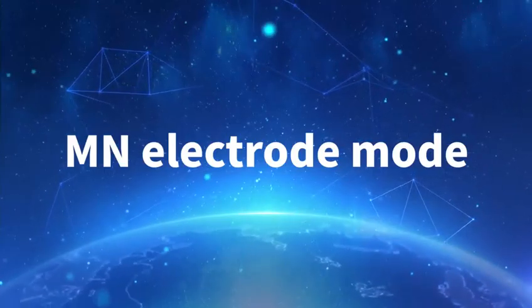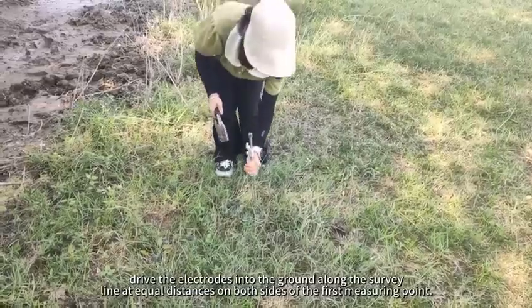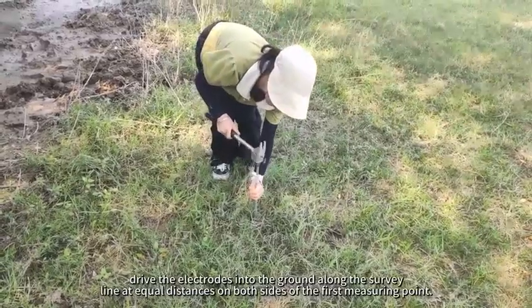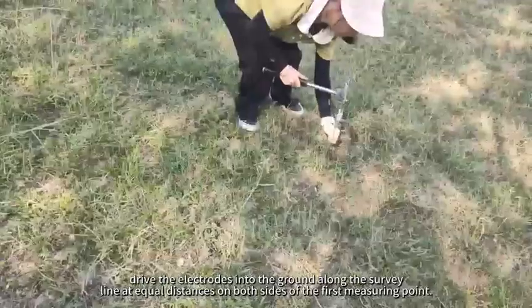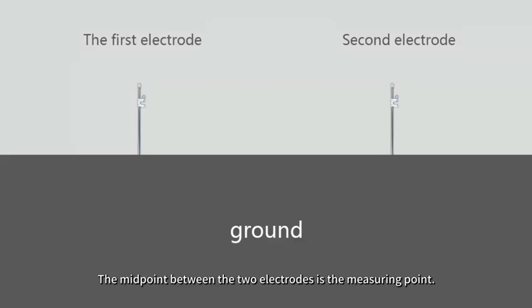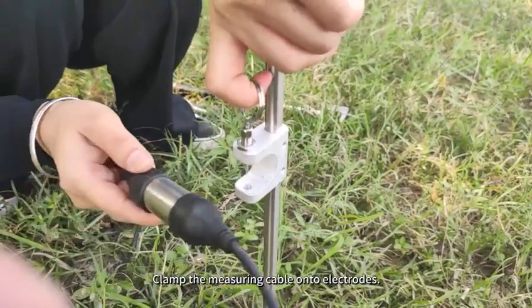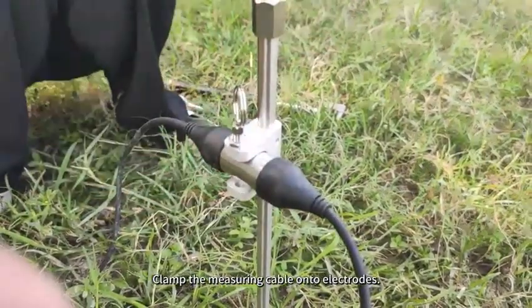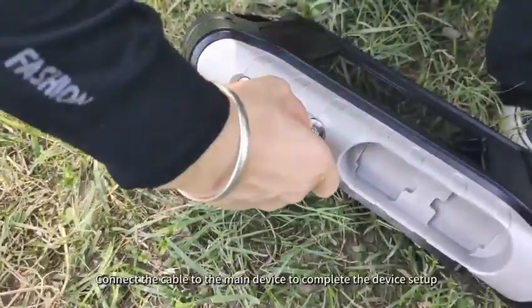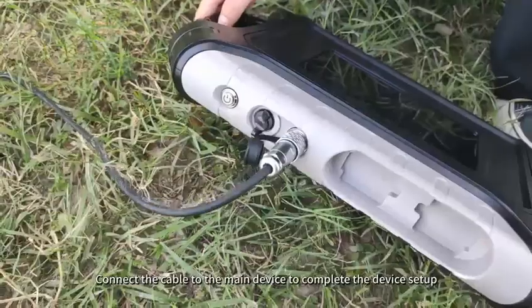When measuring in MN electrode mode, drive the electrodes into the ground along the survey line at equal distances on both sides of the first measuring point. The midpoint between the two electrodes is the measuring point. Clamp the measuring cable onto electrodes. Connect the cable to the main device to complete the device setup.